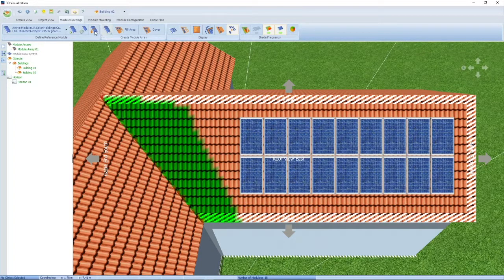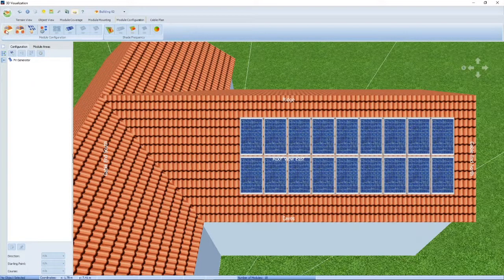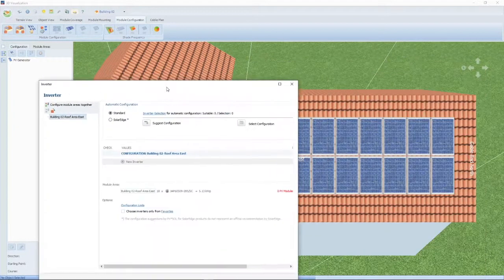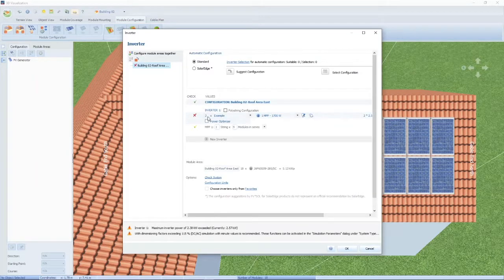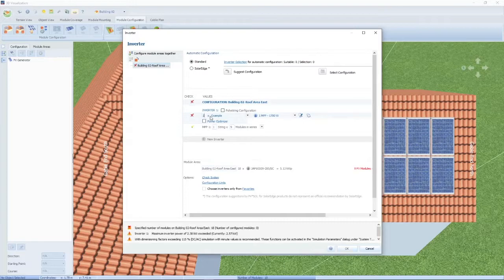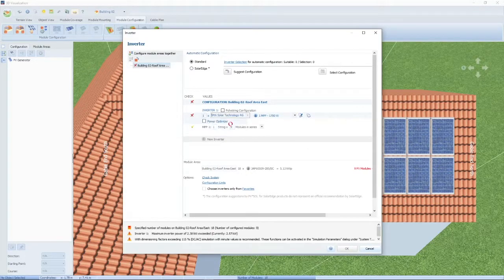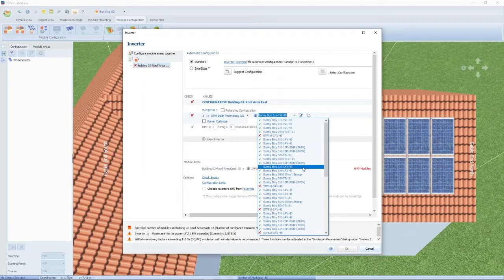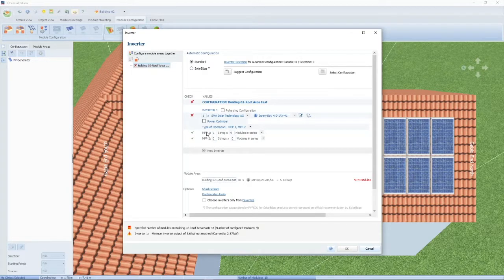Once the modules are on, we can move to the next step — module configuration. This is basically where you select the inverter. I'm going to add a new inverter — one inverter, selected from a database. I'm going to use an SMA inverter, about a 4-kilowatt SMA inverter. This inverter has got two MPP trackers and we can now specify how many modules per tracker. We've got 18 modules.